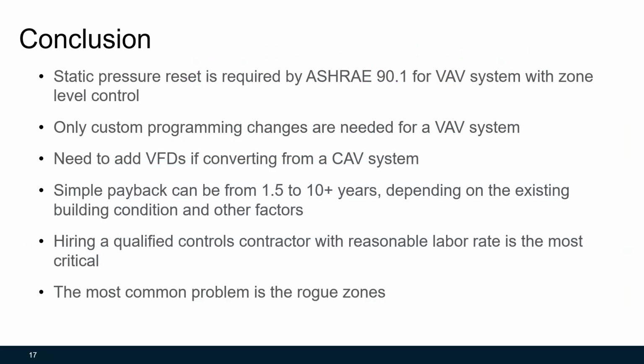Here's the summary of this ESTCP demonstration. Static pressure reset is required by ASHRAE 90.1 for a variable air volume system with zone level control. Only custom programming changes are needed for a VAV system, and you need to add VFDs if converting from a constant air volume system. Simple payback can be from 1.5 years to 10 plus years, depending on the existing building condition and other factors. Hiring a qualified controls contractor with reasonable labor rates is the most critical factor.